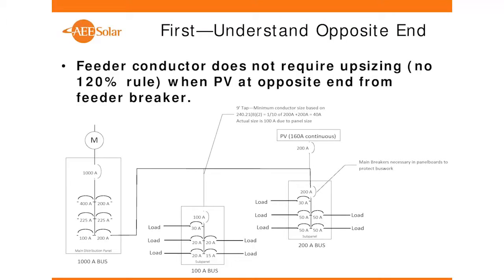So now we've got our main panel over here and our sub-panel over here, and we connect right before we get to the sub-panel. We connect the PV system in there. Well, the power can go this way into the sub-panel, or if there are no loads in the sub-panel, the power can go this way back to the main panel. They can't go in opposite directions at the same time, and the feeder only has to be sized for the larger of those two calculations.